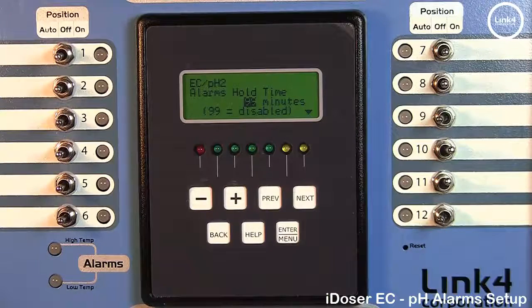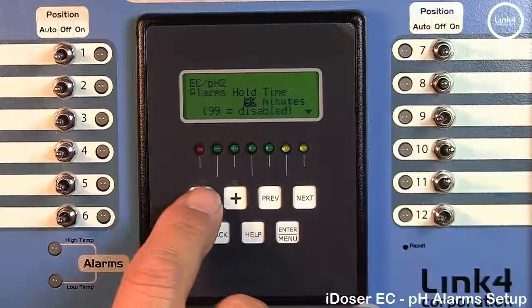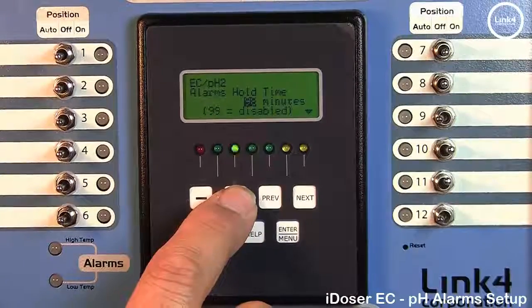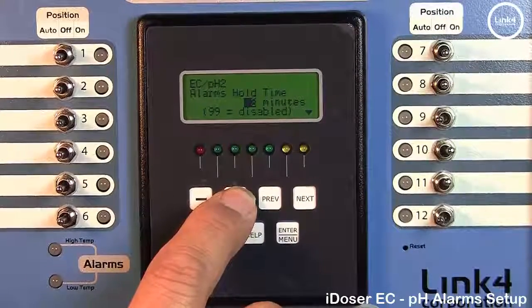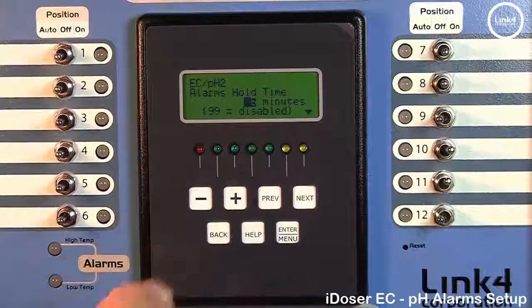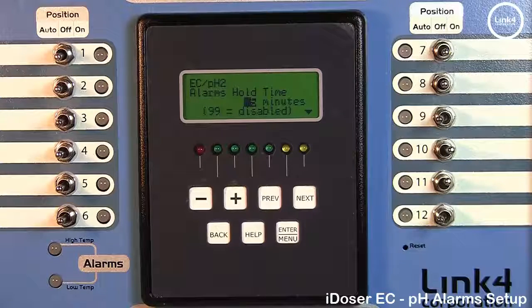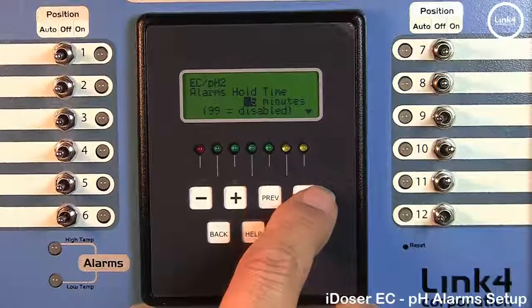Now the hold time lets you choose how long you want this condition to exist before going into the alarm mode. Now 99 is in fact disabled. Plus and minus will change the numerical values. And we'll go ahead and make this 5 minutes. So this means that if the condition exists, it will hold for 5 minutes until the alarm will in fact engage. Hit next to get to the next screen.